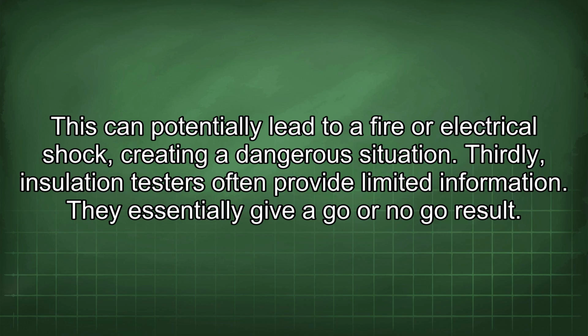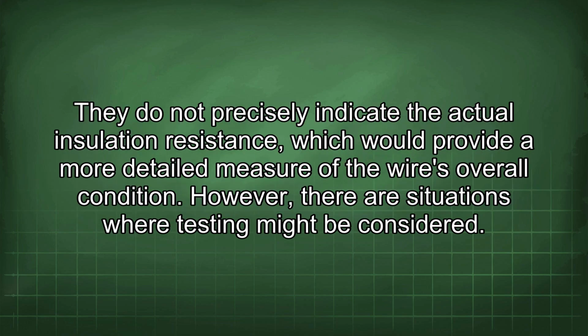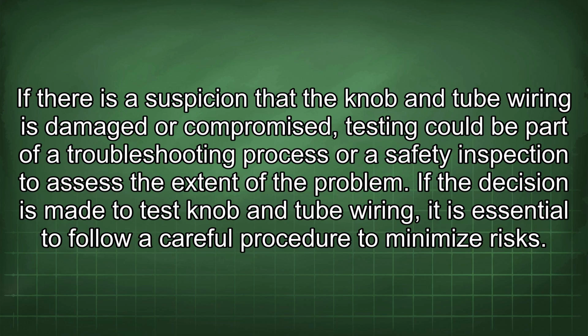Thirdly, insulation testers often provide limited information. They essentially give a go or no-go result. They do not precisely indicate the actual insulation resistance, which would provide a more detailed measure of the wire's overall condition. However, there are situations where testing might be considered. If there is a suspicion that the knob and tube wiring is damaged or compromised, testing could be part of a troubleshooting process or a safety inspection to assess the extent of the problem.